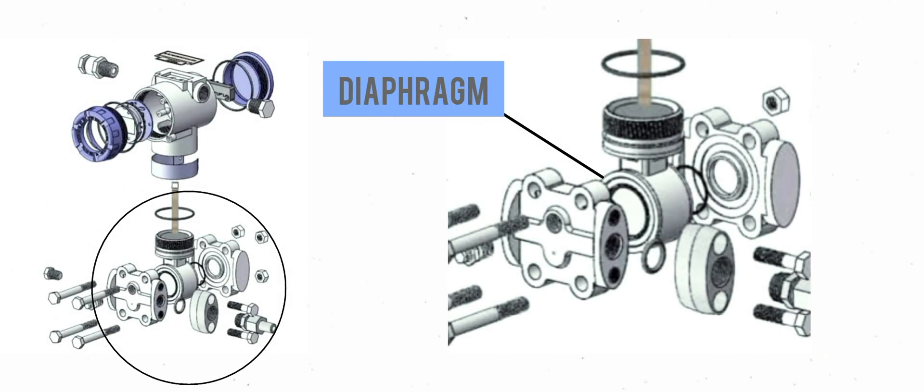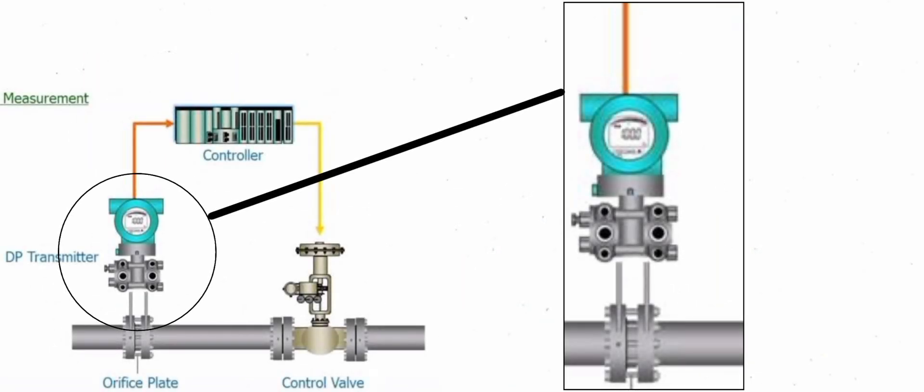The elements in a DP transmitter will have sealed diaphragms and one of several ways to convert the pressure applied onto the diaphragms into an electrical signal. Sensors such as differential capacitance, vibrating wire, or strain gauges are used to produce the electrical signal that will be sent to the electronics system.